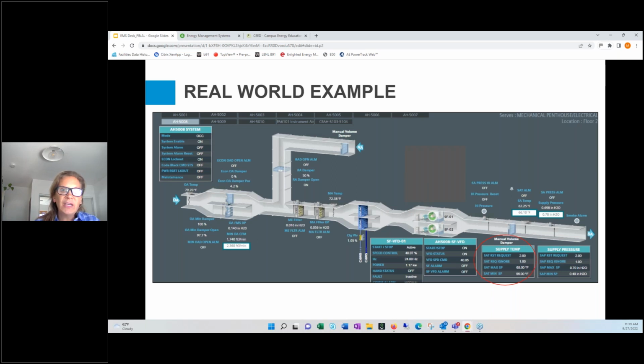one of the energy control strategies that's been around for quite some time is to reset the supply air temperature. And I would say maybe 10 years ago or so, it used to be primarily based on outside air temperature. So if it was hot outside, we would reset the supply air temperature down to 55 degrees. And if it was cooler outside, we would allow it to rise up to, let's say, 68 degrees. And by doing that, we should be saving some energy. So that is one strategy. Now, as we've continued to look for more and more ways to save energy, we came up with a different way, or what could be called a better way.